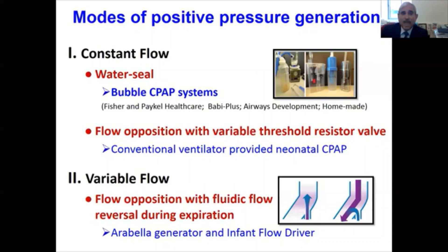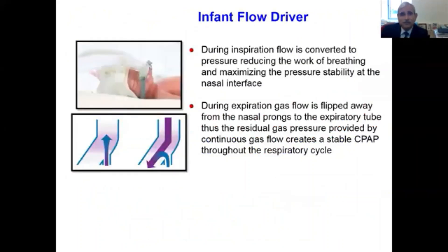In the variable flow system, gas is entrained during inspiration to maintain stable pressures, and during expiration the expiratory flow is diverted via a separate fluidic flip-flop valve. The Arabella generator and the Infant Flow Driver are typical examples of this system.